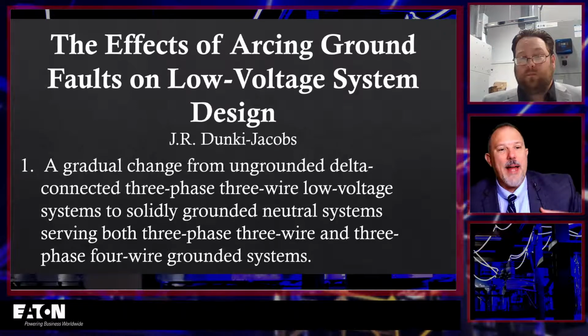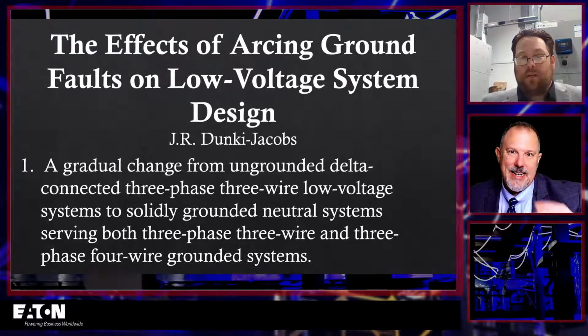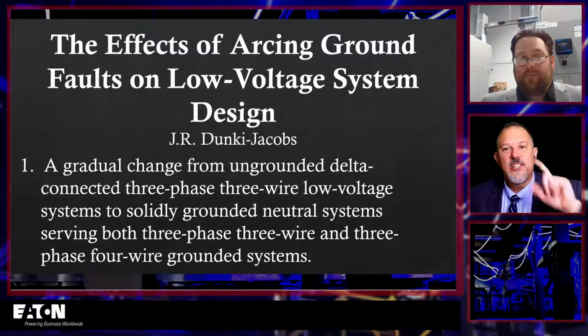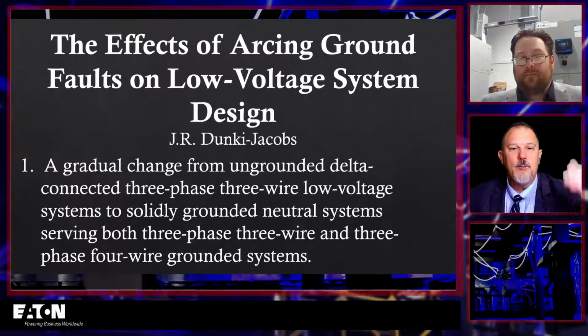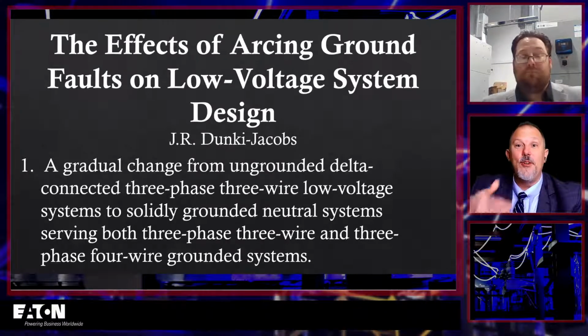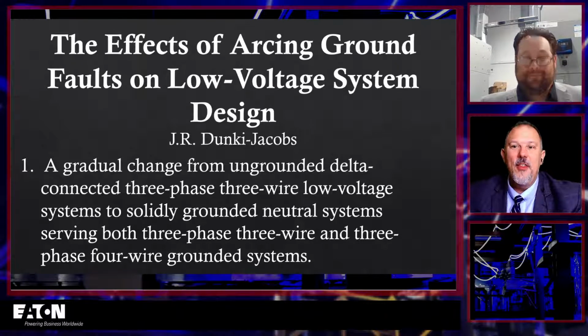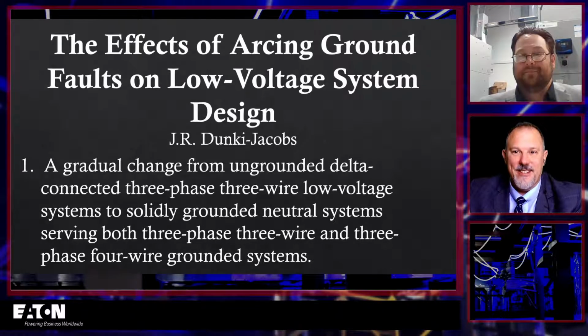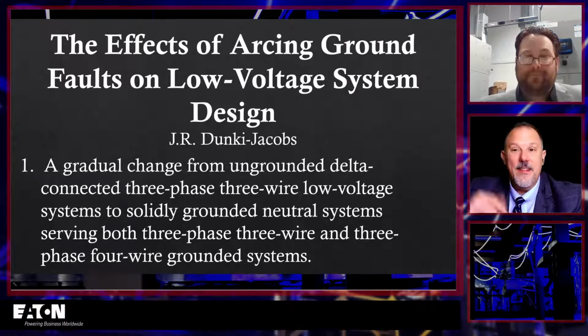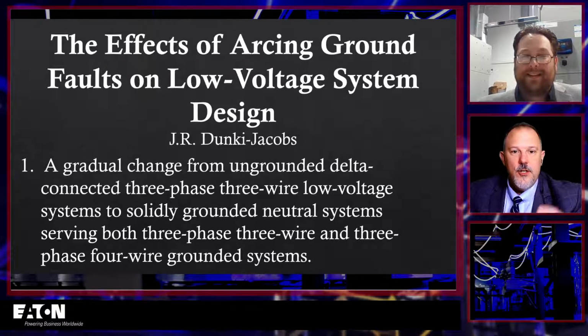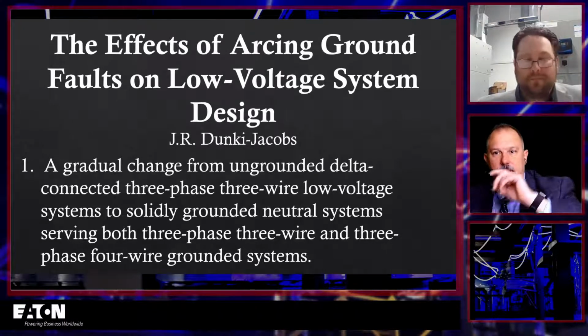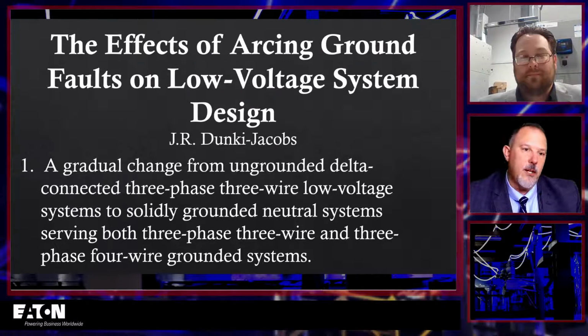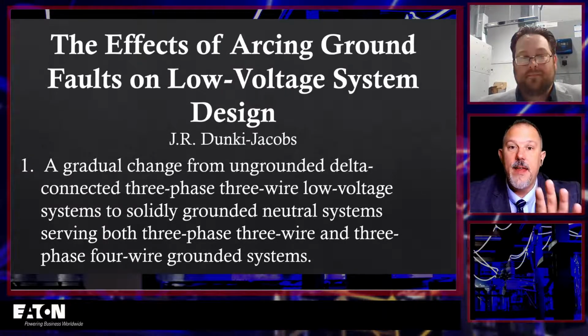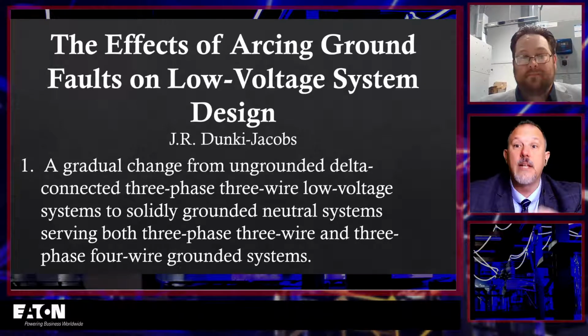And I'm not sure who came up with the idea, and I'm still trying to figure this one out, but somebody had the bright idea to say, I'm going to ground this system. They probably did a corner grounded delta system, right? Because what happens when you have that first fault in an ungrounded system? It becomes a grounded system. Okay. Yeah. And then the second fault's always the doozy. So what they were experiencing back in the day, in the 50s and 60s and into the 70s, was a gradual change from an ungrounded system to a grounded system. And that means that first fault, to your point, is a doozy.